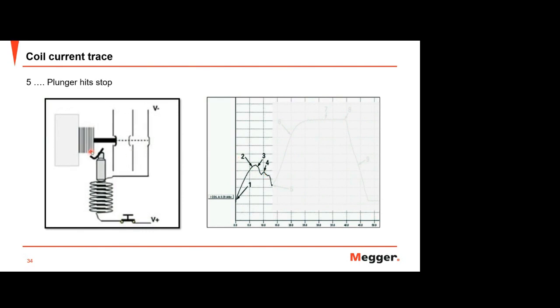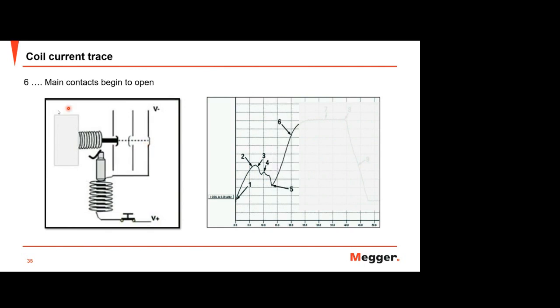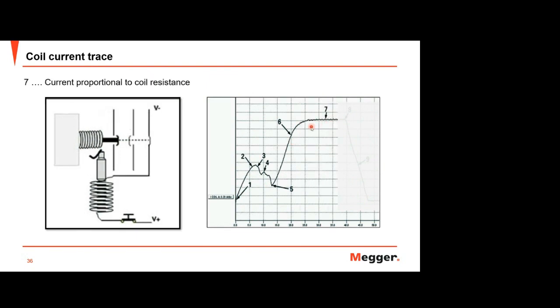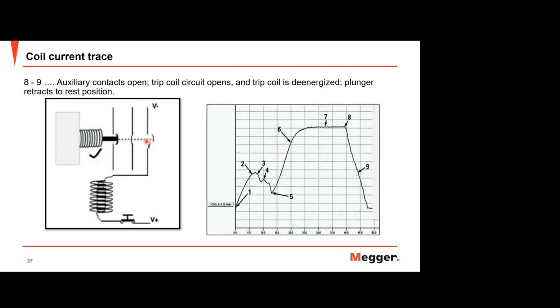Now, because there is no latching holding the spring, the spring will move to the right, the plunger stops, and then the main contact begins to open. So it pushes the spring to the main contact of the breaker, and the breaker contact opens until this point 7. So this is the saturated condition where the coil is energized and the current is proportional to the resistance of the coil. You can measure resistance at this point. So when the auxiliary contact here opens, the coil current will go to zero. So this is the illustration of how coil current can give you information about the breaker.